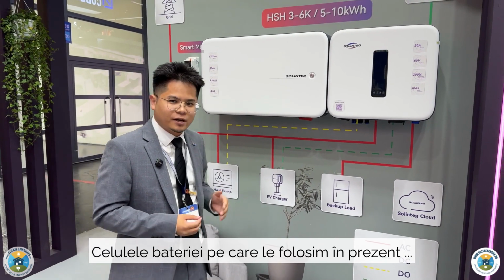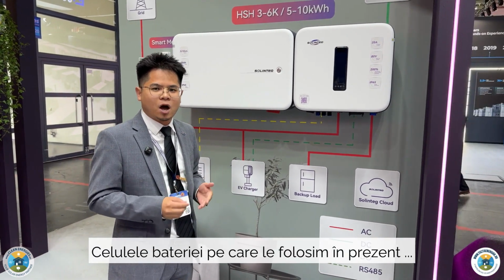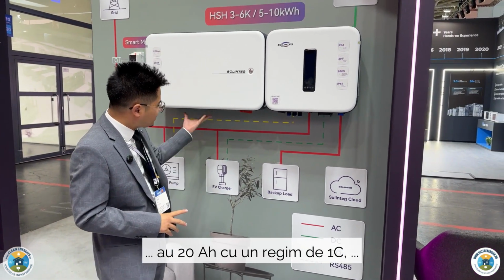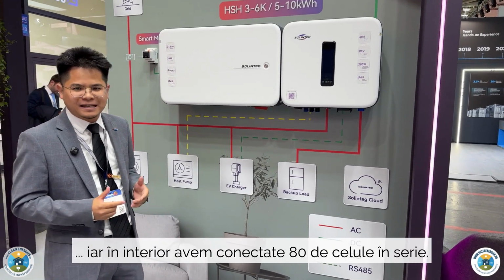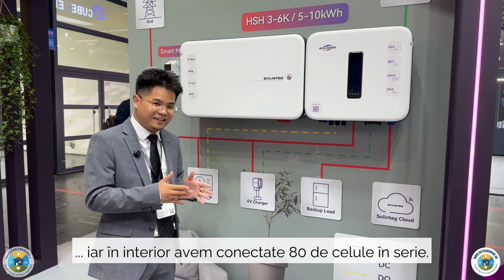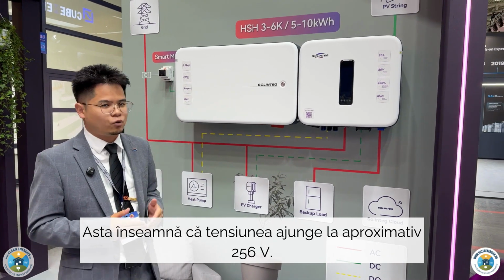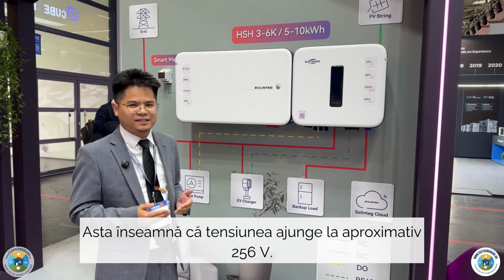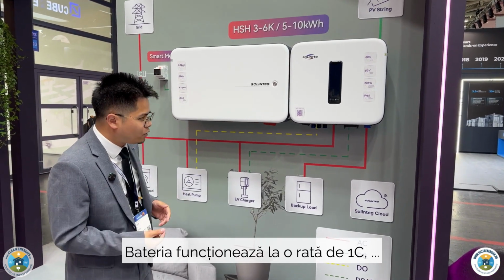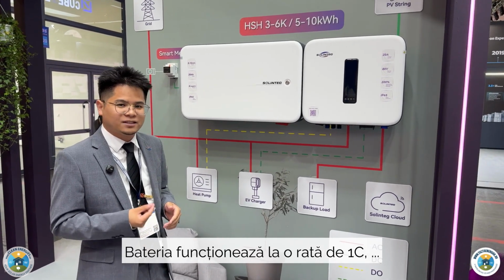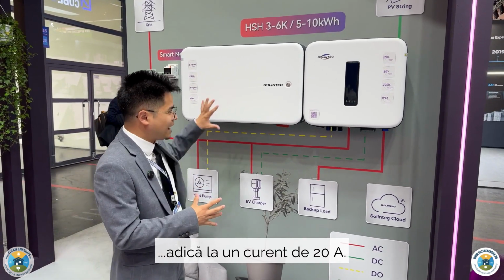The battery cells we use right now are 20 amp hour with 1C rating. Inside, we use 80 pieces connected in series, so the voltage is around 256 volts. The battery's current is 1C, meaning 20 amps. So this is the battery side.